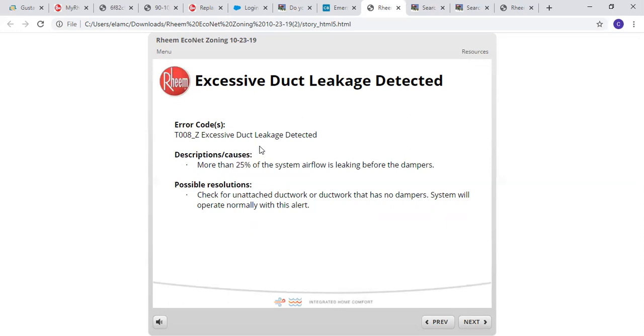This system here will recognize that you have, in this case here, massive amounts of duct leakage, because not every duct is zoned, and you will get this code. So in this case here, more than 25% of the system airflow is leaking before the dampers. Check for unattached ductwork or ductwork that has no dampers. System will operate normally with this alert, but a lot of times you can get some slightly erratic operation. We saw one that did that. But make sure all your ductwork has dampers in it, and that will prevent this excess leakage fault.